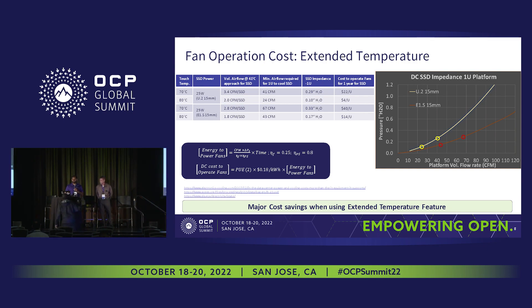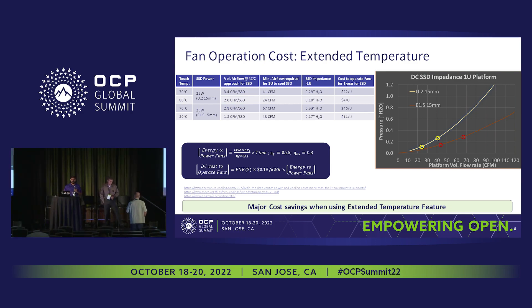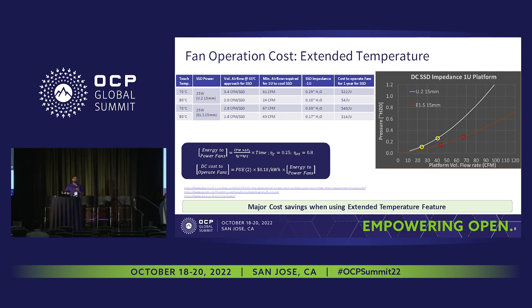On the plot, it also shows what is the impedance of U.2 and E1S at 15 millimeter. The two circles show what is the impedance corresponding to 70 C and 80 C. As you start increasing the platform CFM, the impedance keeps going up, and basically your fans are going to pull more and more power to operate. We did simple calculations using a PUE value of 2 for an air-cooled data center, coming up with CFM and pressure drop and fan efficiency. These numbers are purely for the SSDs — to cool an SSD, how much fan power will be extracted, and coming up with the cost of those.